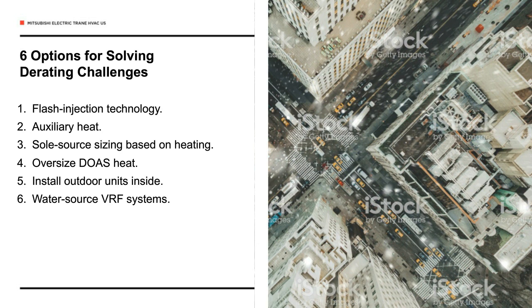Number 4, oversizing the DOAS heat. Most of these shown here are mutually exclusive to each other, with the exception of number 4, oversizing the DOAS heat. That's one that can be used in conjunction with some of these other approaches, and we'll see why when we get to that part of the presentation. Number 5, install outdoor air-cooled units inside the building. And then lastly, install water source VRF systems. So let's talk about those one at a time.